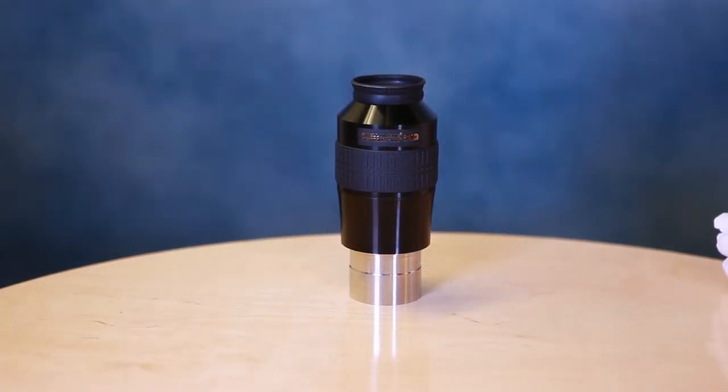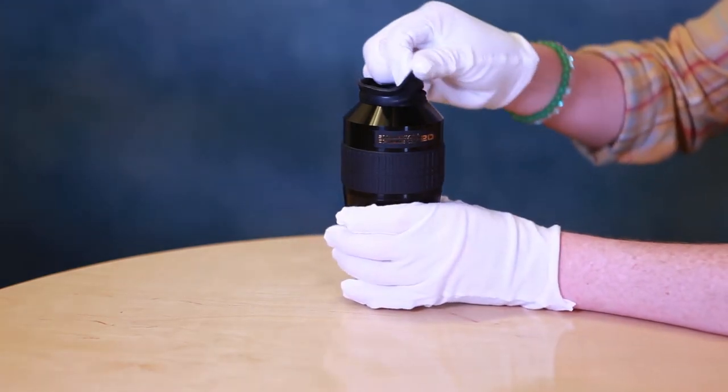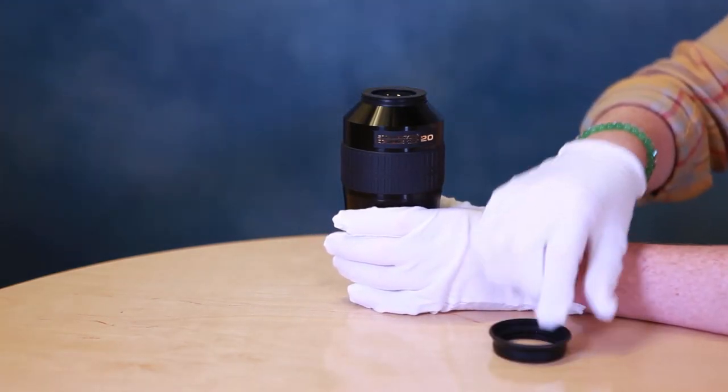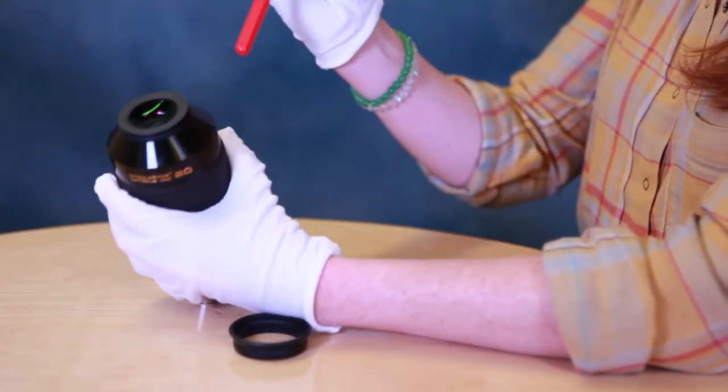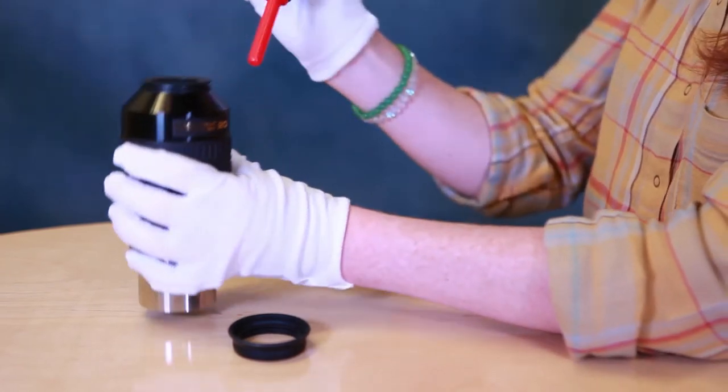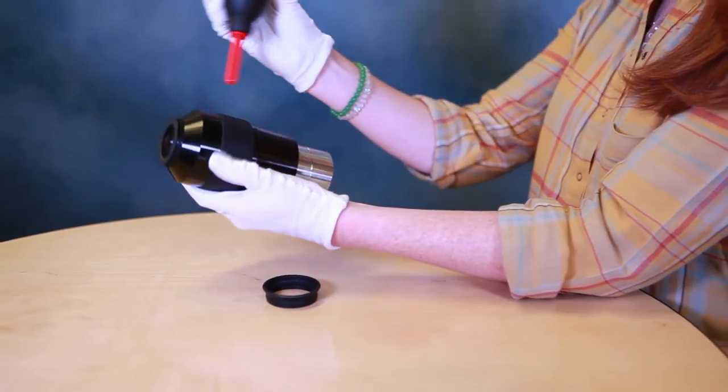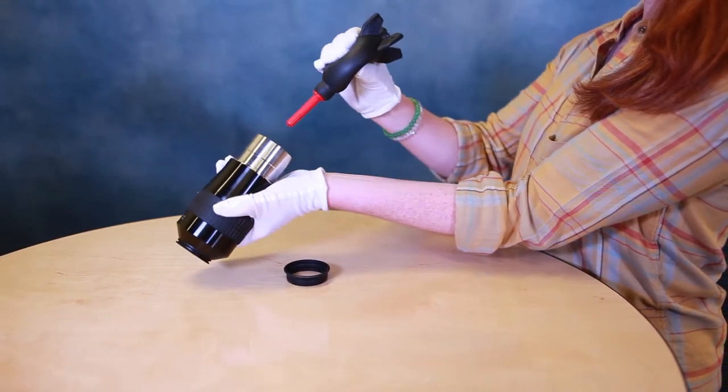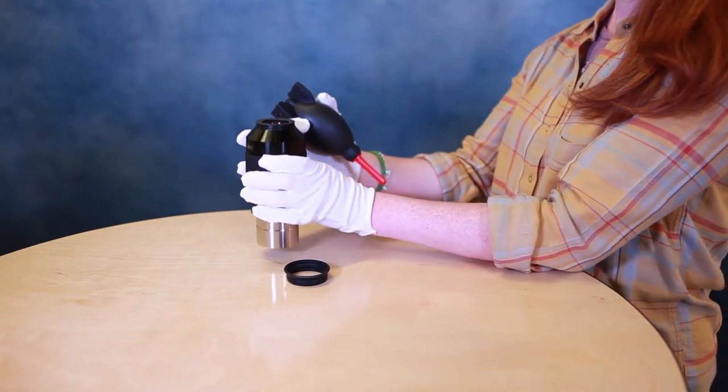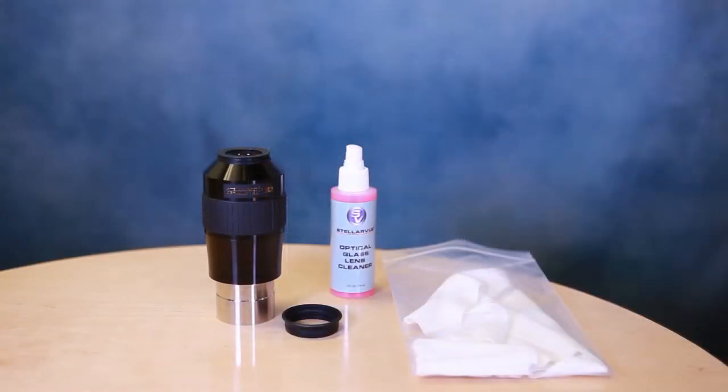Since eyepieces are handled a lot, we feel it's important to start by cleaning the eyepiece's exterior. Most eyepieces have removable eye cups, so remove it first. Then use the bulb blower to remove the loose dust off the exterior of the eyepiece. Get the exterior clean before you attempt to clean the lenses. And while you're at it, blow off the eye cup. You don't want dust and dirt from an eye cup getting onto your freshly cleaned eye lens.